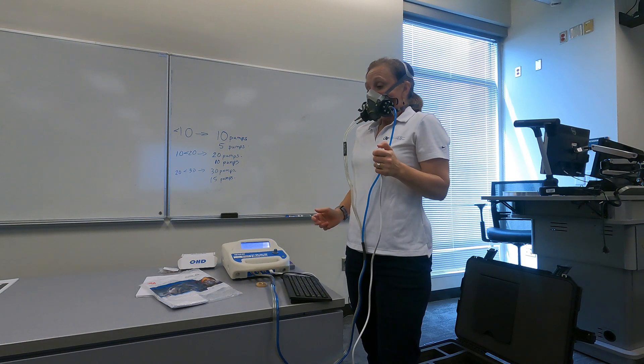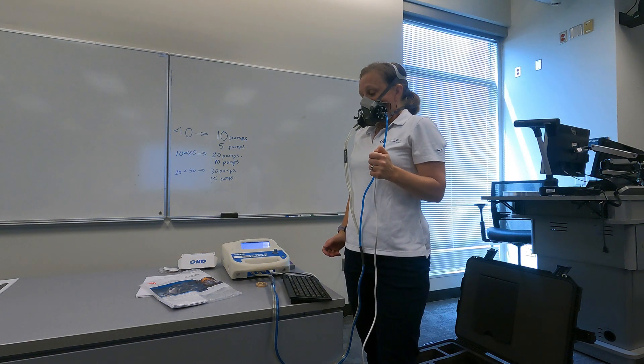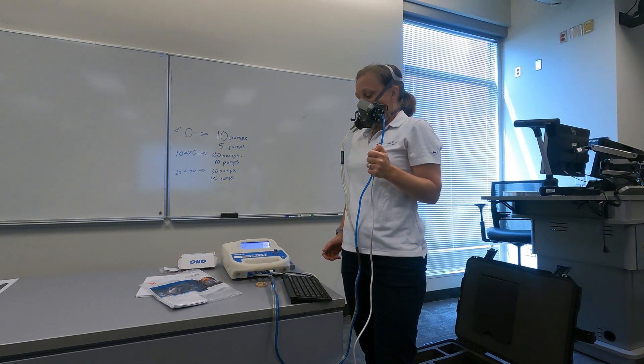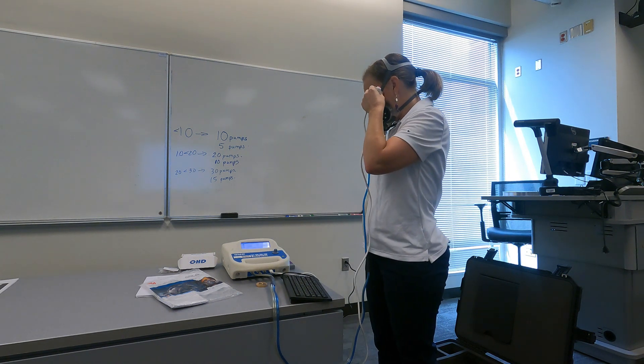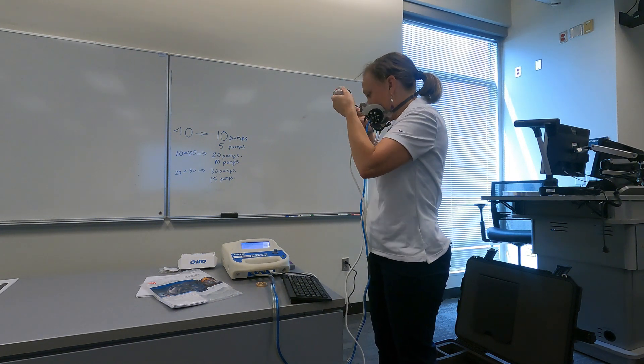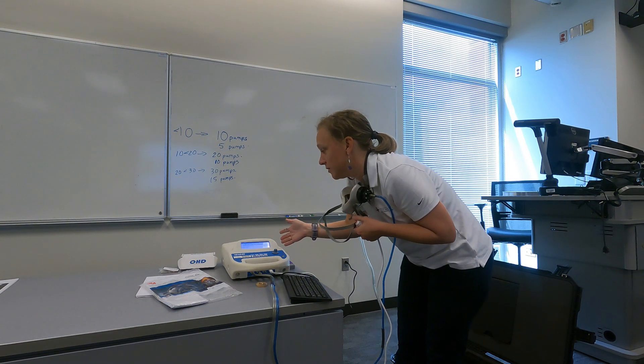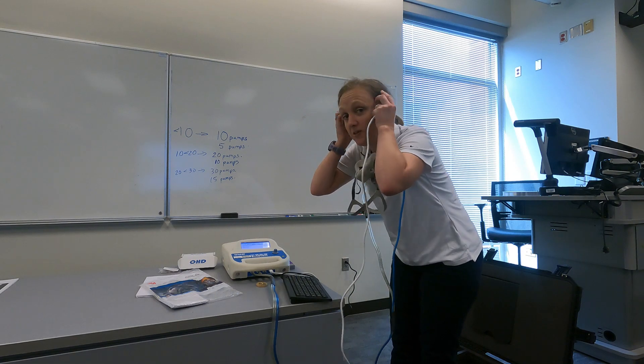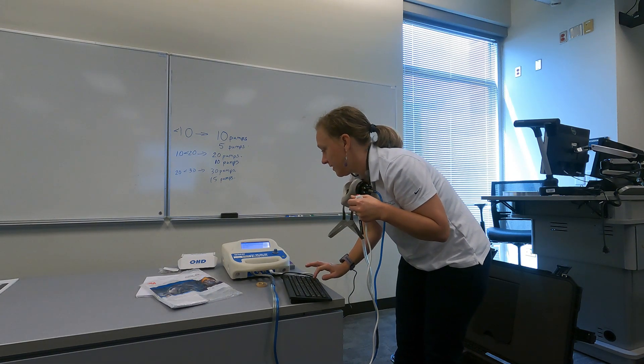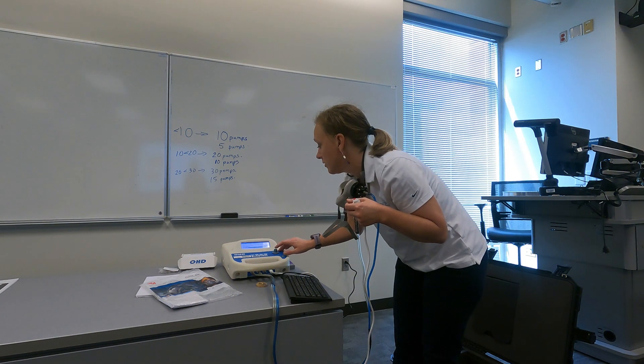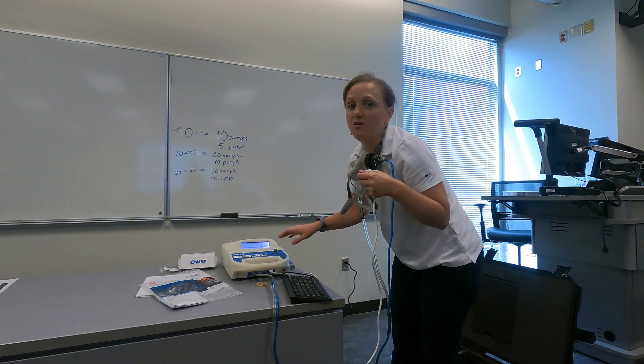I was able to get a successful fit on the mask. It's confirming the mask setup and will then allow me to print out the results of my fit test.